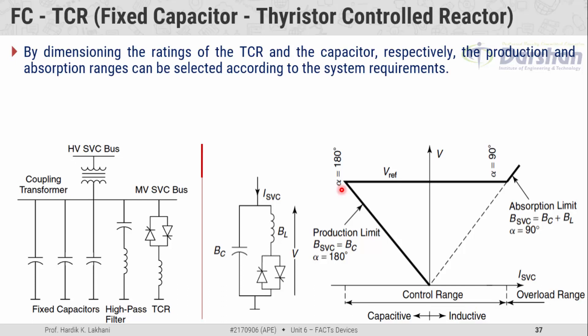By dimensioning the ratings of the TCR and the capacitor respectively, the production and absorption ranges can be selected according to the system requirements. The limits on the capacitive and inductive regions depend on the ratings of the inductive and capacitive elements, and the magnitude of the firing angle of the antiparallel connected thyristor pair. The FCTCR extends the volt ampere reactive range in the leading power factor compared to using only a thyristor controlled reactor.